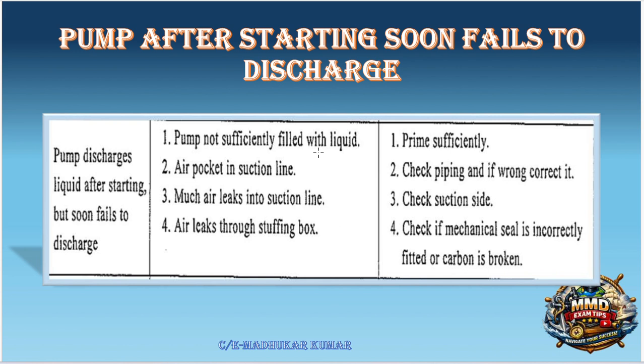Pump after starting soon fails to discharge. Means in the initial stage the pump is discharging, but after some time it stops. What is the problem? The pump is not sufficiently filled with liquid, means whatever liquid was there, it was discharged, and now there is no suction. So then again, priming is required, and make sure that the pump impeller is fully submerged. Air pocket in the suction line, again the priming is required, and remove the air pocket. Much air leak into the suction line, the gland side or any other flange side or somewhere. If the suction is there, check it out and eliminate that condition. It will work properly. Air leaks through the stuffing box.